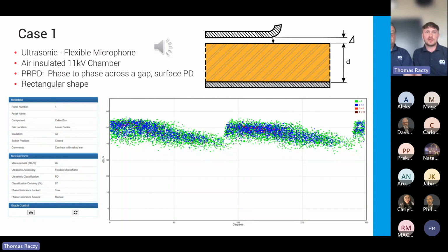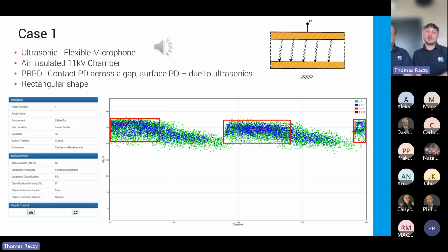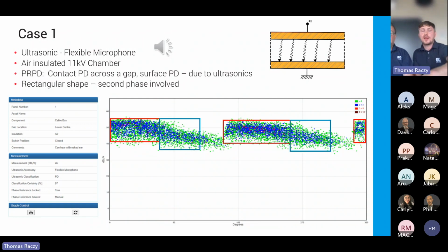So the first case study, the signals were recorded with flexible microphones, so ultrasonics outside of the insulation, and you can see this is a typical pattern for the gap, surface gap, contact gap discharge. That was from an air insulated 11 kV chamber. If we look at the patterns, we've got this rectangular distribution of the pulses, tight clustering. So that's potentially discharges from one phase, and the other group is probably the other phase discharging at the same time.